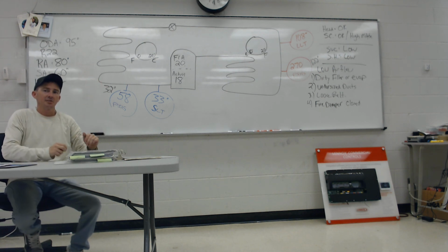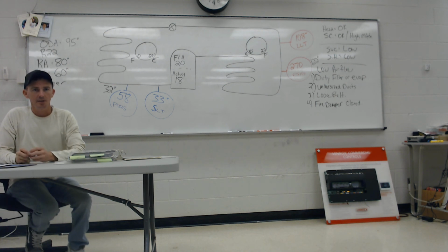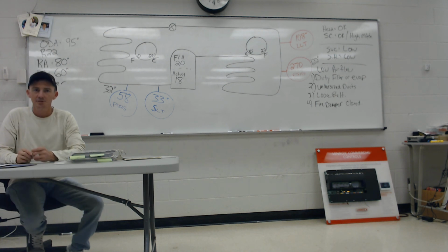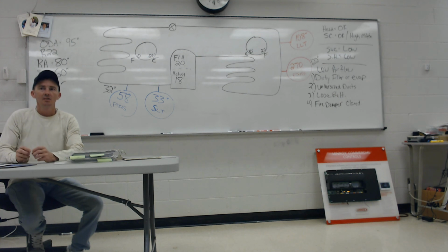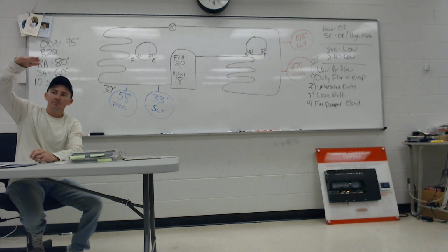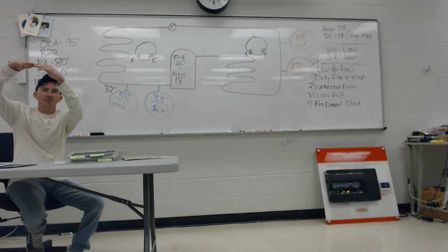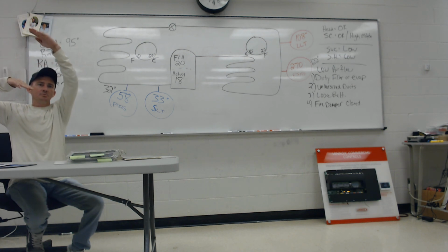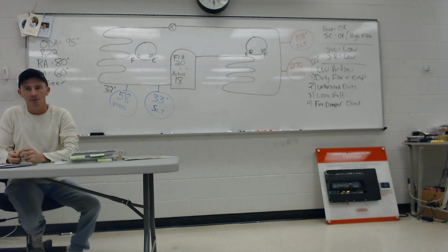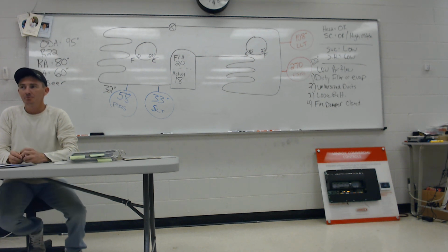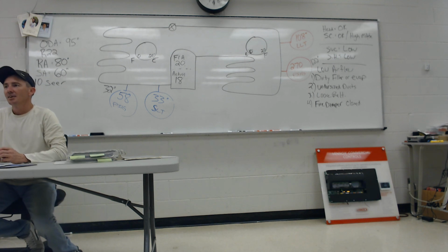An 8-inch is exactly half of that. So how much air will an 8-inch move? 200 CFM, half a ton. So a 10-inch is 400, 8-inch is 200. What about a 12-inch? It's double, so it'd be 800. And then you can get into all the other stuff. Is that for flex duct? It's all about the static pressure, but for rules of thumb, I would use that.